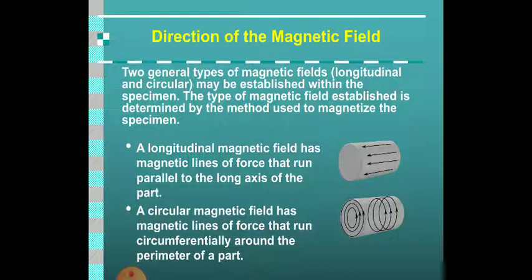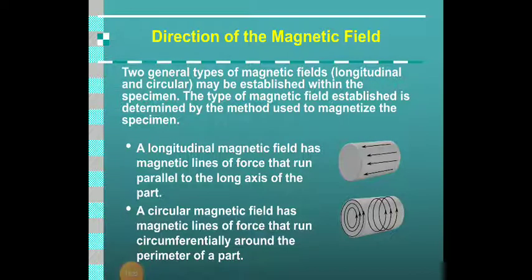And these methods of introduction involve two kinds of method of operation to achieve the best result in magnetic particle testing. It is essential to orient the lines of magnetic flux in a direction perpendicular to the discontinuity or the defect. So this is usually obtained by employing two magnetization techniques.